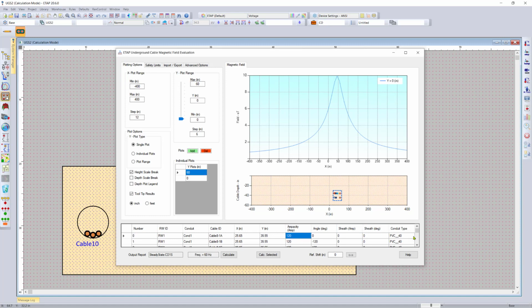You can simply look at the results from load flow and use it to compute your magnetic field strength, or you can have the ability to manually change it as well. You can plot a single magnetic field strength at a certain depth. You can also ask the program to give you individual plots at different depths by simply selecting the depth level and adding it to your chart. Or you can simply ask the program to give you the complete range, in which case you can use a fixed step and see the complete intensity at different depths throughout the underground raceway system.